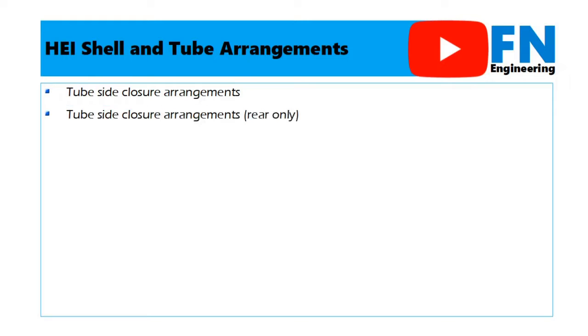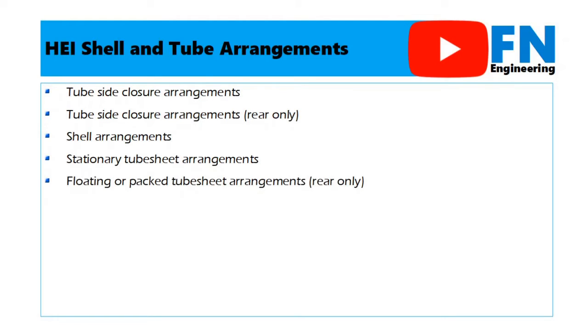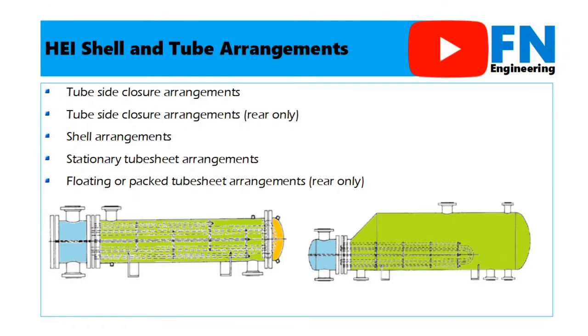Alright, in this video, I would like to describe the shell and tube heat exchanger arrangement based on the Heat Exchanger Institute or HEI standard. The classification of shell and tube heat exchangers is grouped into 5 parts: tube side closure arrangements, both in the front head and rear head; tube side closure arrangement for rear head only; and shell arrangement, not like in the TEMA type. The Heat Exchanger Institute type adds classification for the stationary tube sheet arrangement and the floating or packed tube sheet arrangements. For detail, I will explain in the next slide.